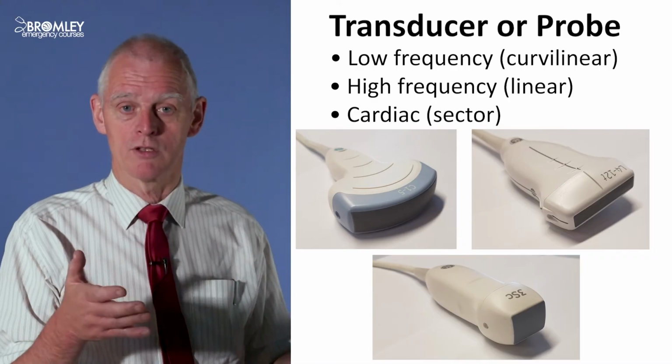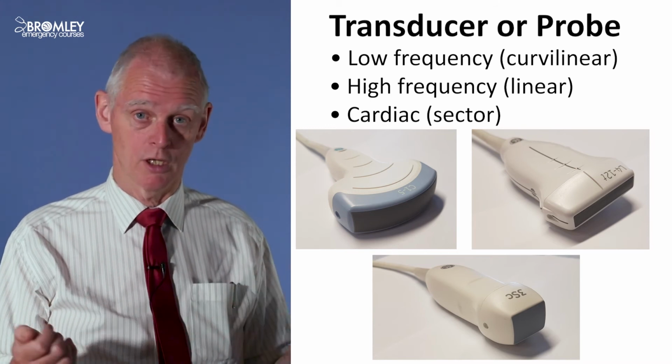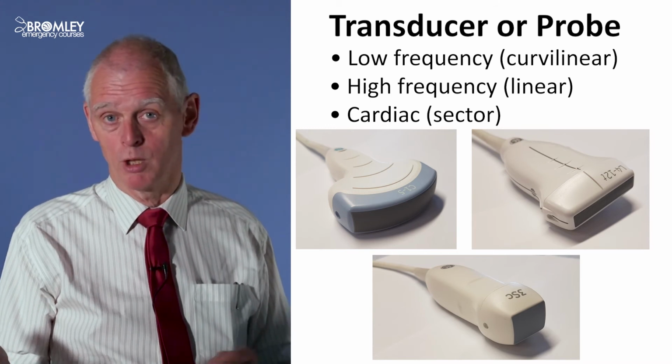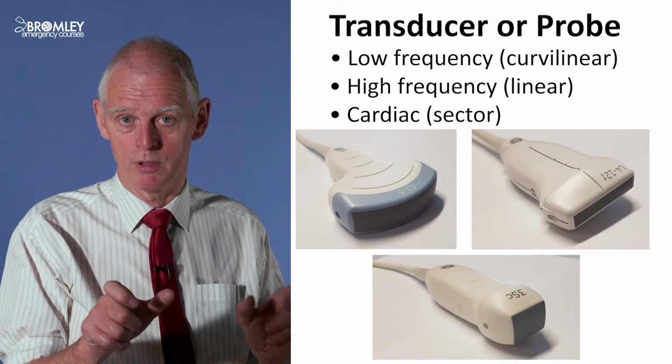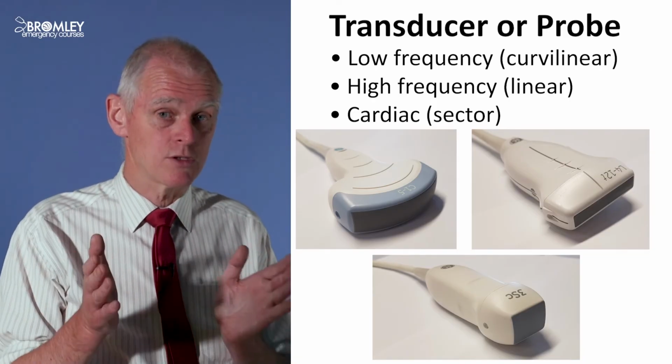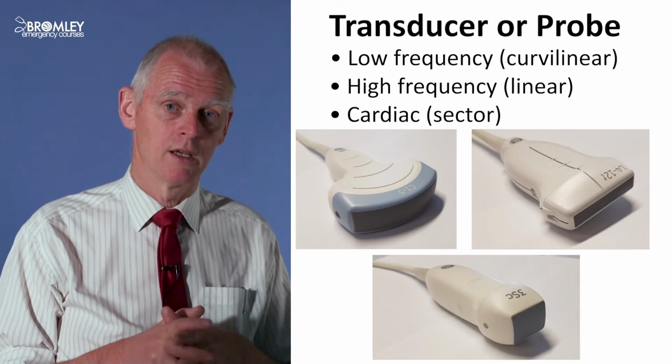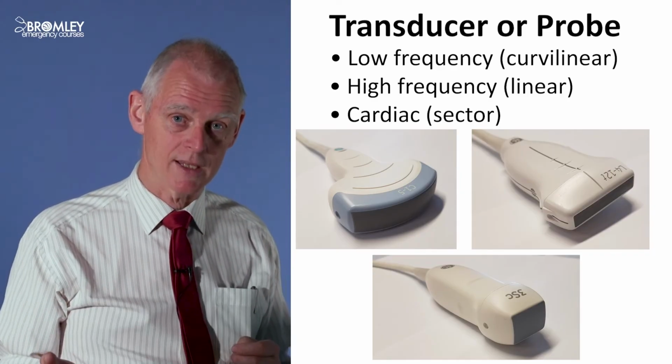However, you might think, okay, so they produce the same images then, curvilinear probe or a phased array probe. You'll get the same image, just a different shape image on the screen. Well, in fact, that's not true. There's a bit more to it than that. And this is where the subject of presets comes up. If you turn on any ultrasound machine and choose a probe, as you choose the probe, it will usually ask you, what do you want to use the probe for? So are you going to use this vascular probe to look at a blood vessel, or are you going to look at the lung, or are you going to look at soft tissue, etc.?